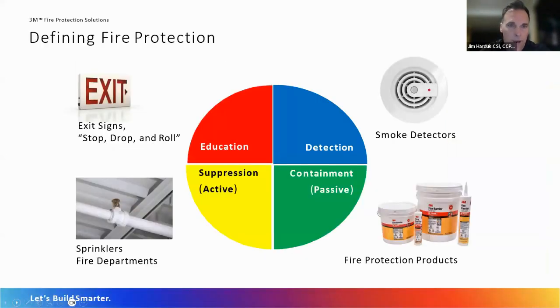So when we're talking about Firestop, we're actually talking about a four-prong approach to fire protection. And that consists of education, detection, suppression, and containment. Education is pretty obvious. You go to most commercial buildings and you look around and you can see that the fire exits are clearly marked, right? So there's signage in buildings that show us where to exit in the event of an emergency. And depending upon the size and type of building, you may also find plaques on the wall showing a map to the nearest exit point.